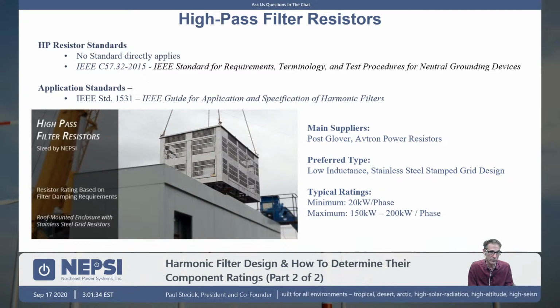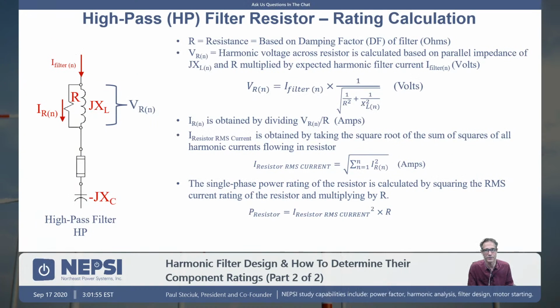And if your filter design, as you're doing your harmonic analysis, is starting to get, and this would be maybe for a very large mine project, if you're starting to get up into that maybe 180 kW, 200 kW range per phase, it means your design should change. It really means that you have to take a different approach in your design because the ratings are getting a bit high. So we won't go through this in detail, but we do give the formulas here.